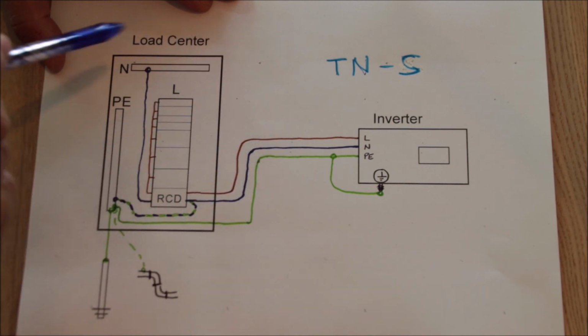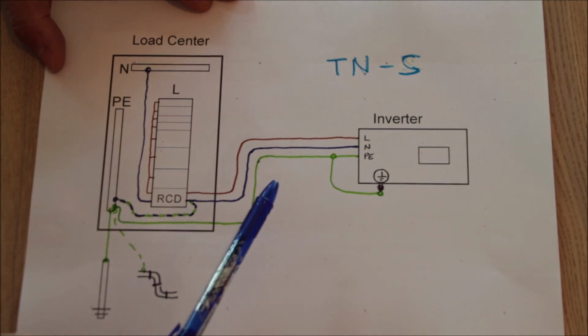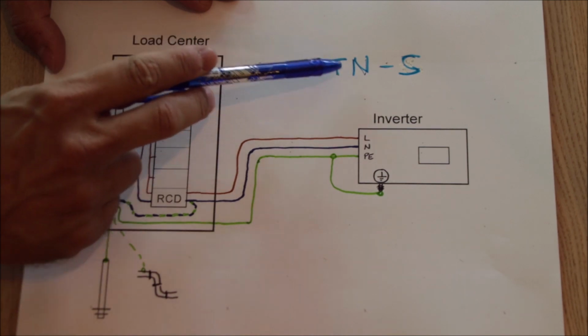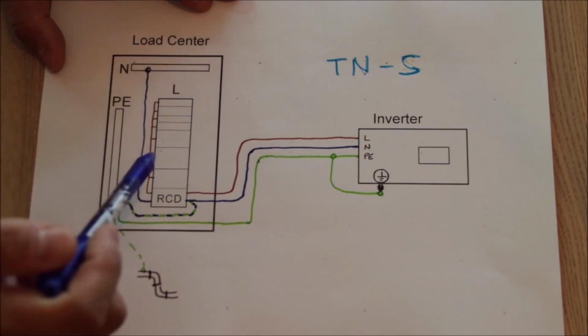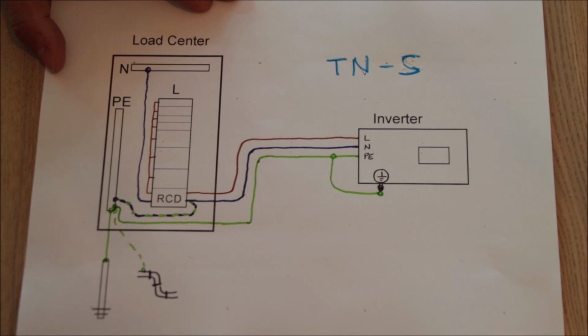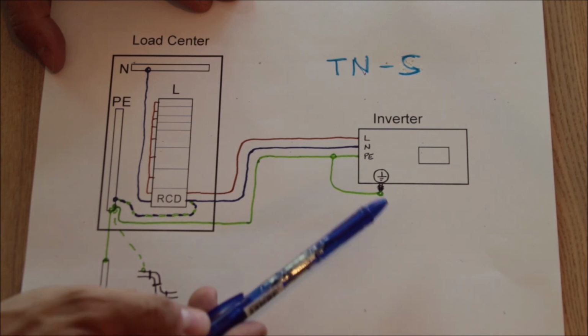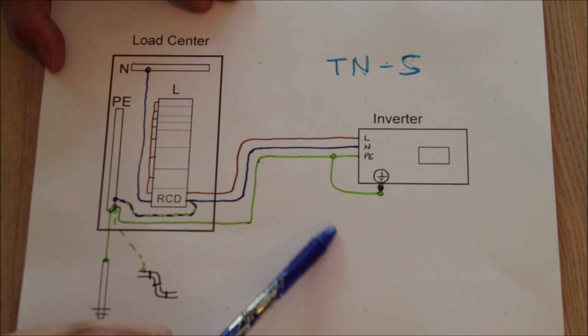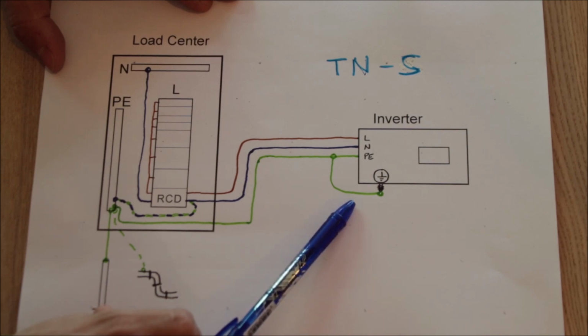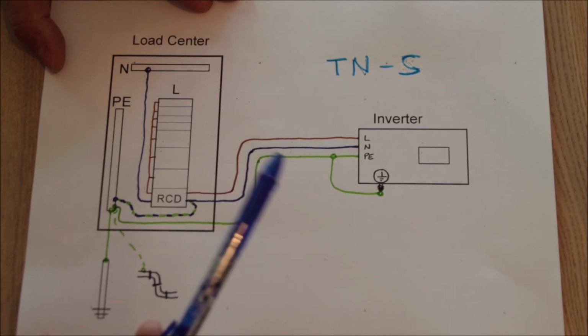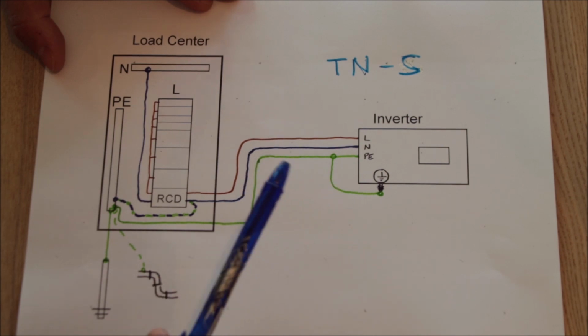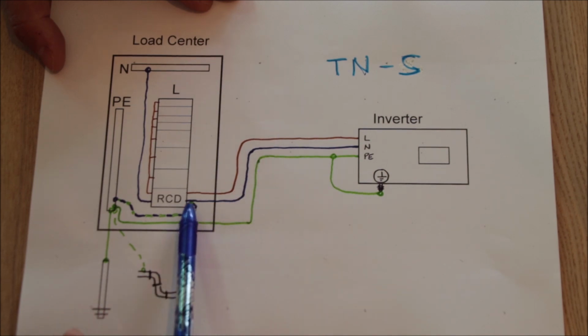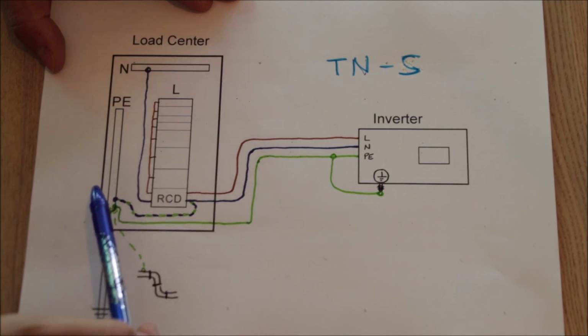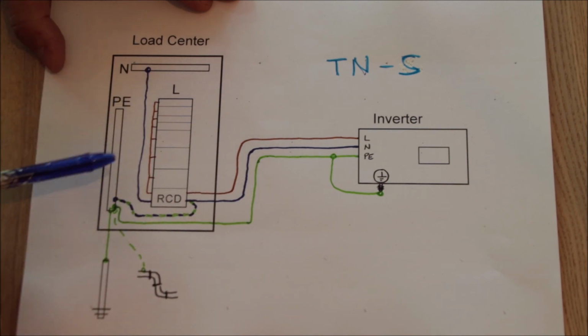So we have a double protection in the TNS system, so that's why we go for this one. But you will see the bonding, usually TN means that the earth and neutral are bonded at the source of the power, and that would actually mean, if you see it correctly, that the bonding would have been done somewhere here already, right at the inverter. But we are not going to do this, for obvious reasons, because the connections can be much easier made and more solid inside the load center.